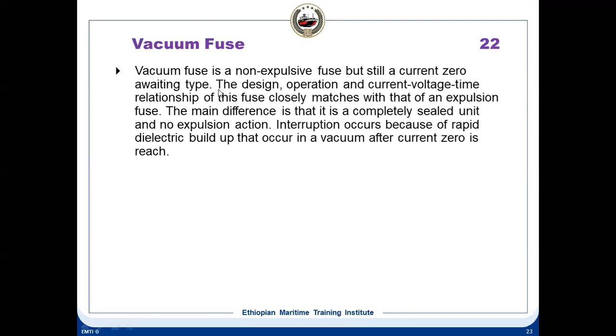So this is another type of fuse. It's a vacuum fuse. Means inside is a vacuum. As you have seen in vacuum circuit breakers and all, it's 10 raised to -4. So the dielectric property is very high in the case of vacuum, much more than the air. So this is the way it interrupts the current, by having a higher vacuum. Because you see, the current needs a flow of electrons. So when it becomes vacuum, the flow of electrons is reduced.